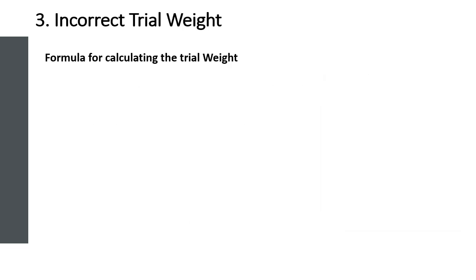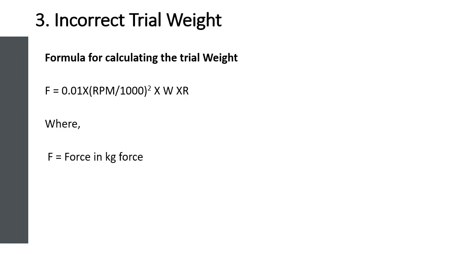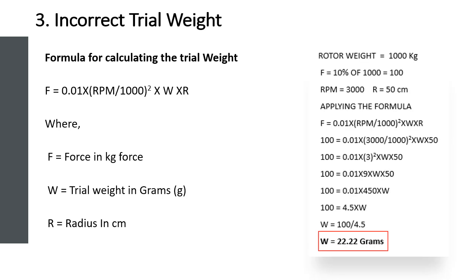The formula for calculating trial weight is based on the first thumb rule. In this formula, F is the force in kgf, W is the trial weight in grams, and R is the radius in centimeters — units can be adjusted as required. For example, with a rotor weight of 1000 kg, the force is 10% which is 100 kgf. With an RPM of 3000 and radius of 50 centimeters, applying the formula gives a trial weight of 22.22 grams.